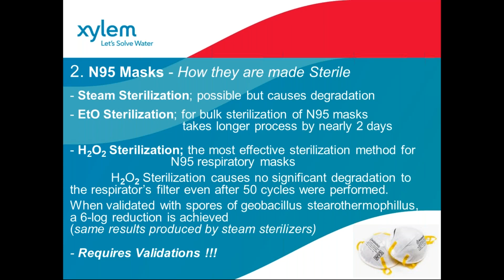Hydrogen peroxide sterilization does not cause any significant degradation to the respirators. It is recommended when validated with spores of Geobacillus stearothermophilus. This is the most common spore strip used to validate sterilization processes. Don't worry, Geobacillus stearothermophilus is a surrogate microorganism. It's not natural, so it is very well handled. Just to mention, when using the same spore strips of Geobacillus stearothermophilus in autoclave operations and in hydrogen peroxide, they both produce the same six log reduction, but they require validation.